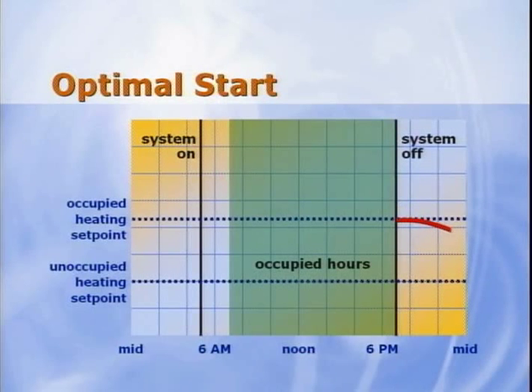Next topic, optimal start-stop. In many applications, a simple time clock or time of day schedule is used to start and stop the HVAC system. This simple set it and forget it logic is reliable and typically works without issue. During the unoccupied hours, the system is shut off and the temperature is allowed to drift away from the occupied set point. The time at which the system starts in the morning is typically set to ensure that the indoor temperature reaches the desired occupied set point on either the coldest or warmest morning of the year. Not a very scientific approach, but no one has to think about what's happening with the system or when it happens. The result is, for most days, the system starts much earlier than it needs to. This control method increases the number of system operating hours and energy usage.